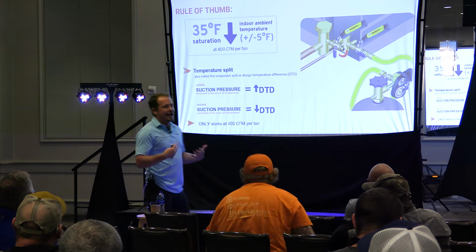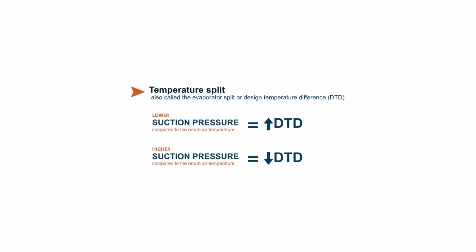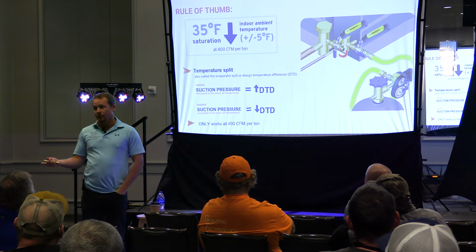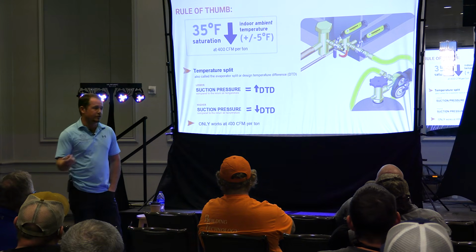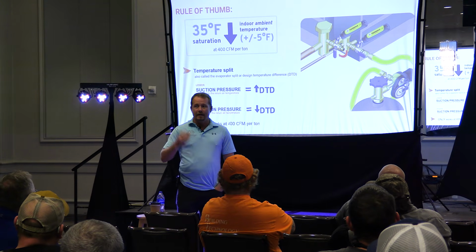Because in our market, we had conditions that he just wasn't used to seeing, these very high latent conditions. And that does drive down the DTD. It drives up the evaporator temperature. But the other reason is that we have more oversized evaporator coils than we had before as well. So that's another thing that's driving it. But it's pretty consistent. It's pretty consistently going to be in that range.